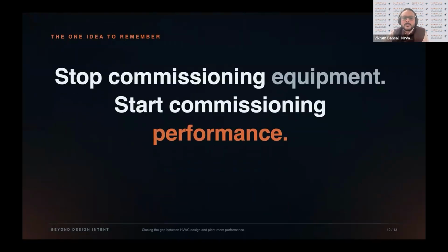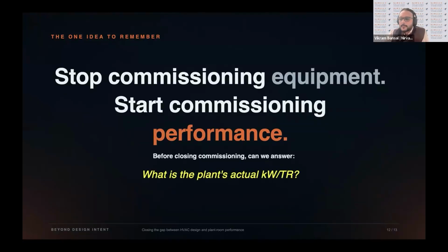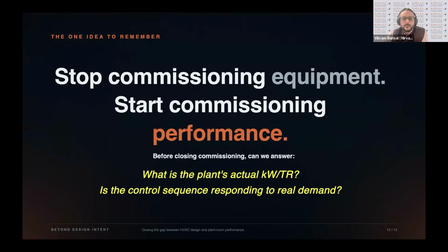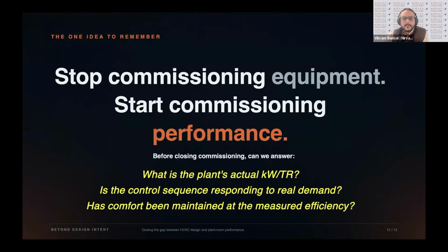I just want my audience to remember one thing: we should stop commissioning the equipment. We should start commissioning the performance. Before closing, we should have an answer to at least one of these three questions. What is the plant's actual kilowatt per ton? Is the control sequence responding to the real demand? Has comfort been maintained at the measured efficiency? So whatever efficiency we have designed, are we able to get the same efficiency without compromising comfort at any point in time?